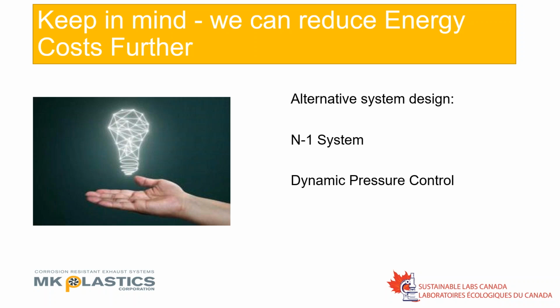So this can be a very advantageous design when you're looking at a BSL 3 or greater lab, because once you start getting into those higher usage labs of more critical environments, the allowable drop in static pressure should a fan fail before the system has to ramp up to full volume is 10 seconds. So that 10 seconds to go from 0 to 100% is not very long, but 10 seconds if you're already at, say, 60% to go up to 100%, now you're going to maintain your static pressure inside that 10 seconds and you will have better control.